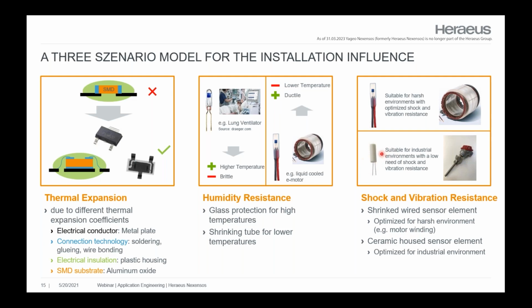In that example, you see protection which withstands temperatures up to 550 degrees, for example. This is a ceramic housed element. It's a ceramic tube, it's a ceramic filling, and our sensor is potted in. But on the other hand, it's again a bit more brittle than the version on top. That means you could not use this version in an electric motor, for example. Sealing is also not as good compared to that shrinking tube version.